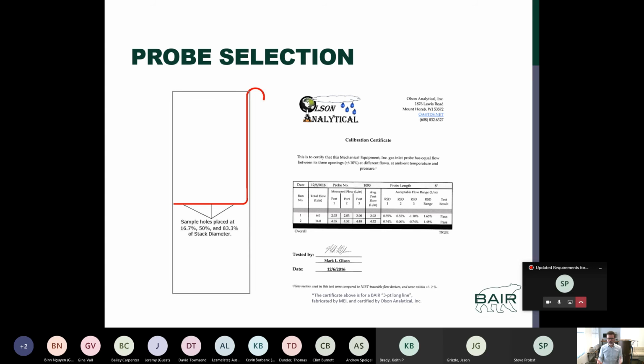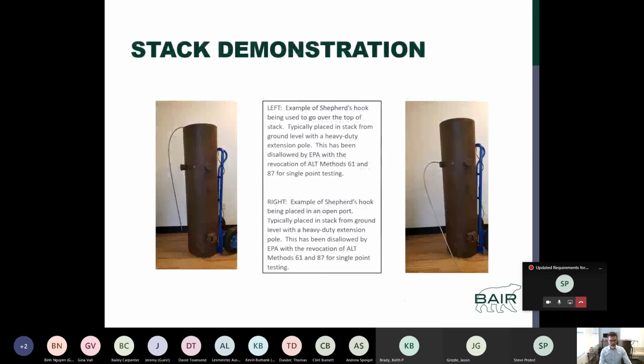The probes that we have were designed by MEI and then sent to Olson Analytical to be certified for the flow criteria. You can certify these if you've got all of your dry and wet meters to do this process. I don't think that your average gas compression testing company is capable of handling this certification in-house. So be aware of that, what type of probe you're using and what scenario you're using these probes.